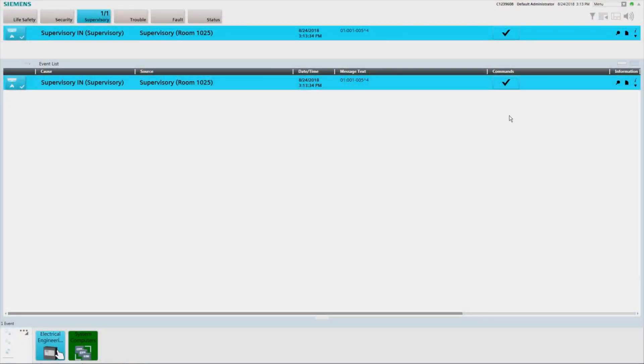A supervisory alarm is indicated in the summary bar by the blue flashing supervisory lamp and the blue flashing fire panel icon in the node map. In addition, a blue event will be displayed in the event list with a blue flashing event icon and the workstation audio indicator will sound. To acknowledge the supervisory signal, press the acknowledge button located in the commands column in the event list. The workstation audio indicator will be silenced, and the supervisory lamp, event icon in the event list, and the source fire panel icon in the node map will change from flashing to steady. When the supervisory condition has been cleared, you may need to reset the panel to restore to a normal standby condition by pressing the reset button.